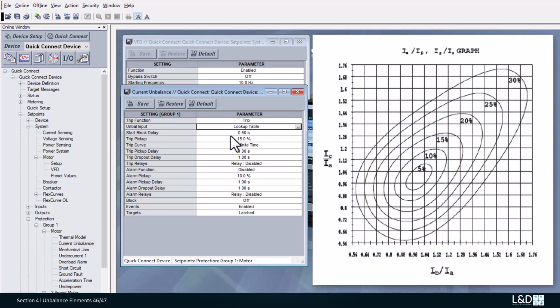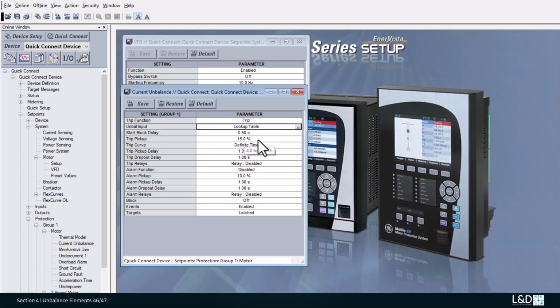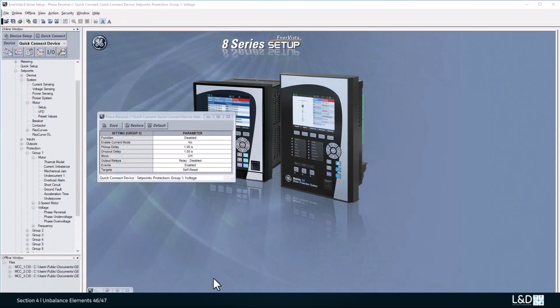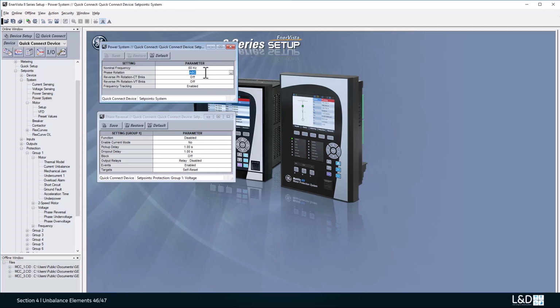In this example, we're going to set the trip to 25% with a time delay of 10 seconds. And for the alarm function, we're going to set 20% and a 10 second delay. The phase reversal function 47 can detect the phase rotation of the three-phase voltage. If the phase rotation of the three-phase voltage is not the same as the phase rotation set under the system phase rotation, then a reverse phase rotation alarm will occur after the delayed pickup.